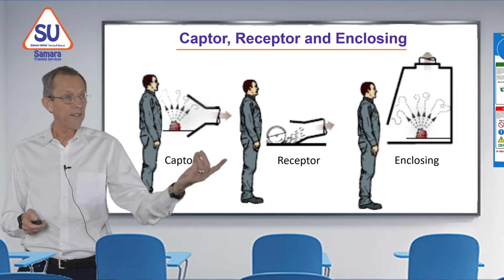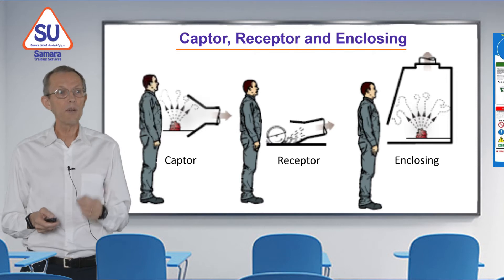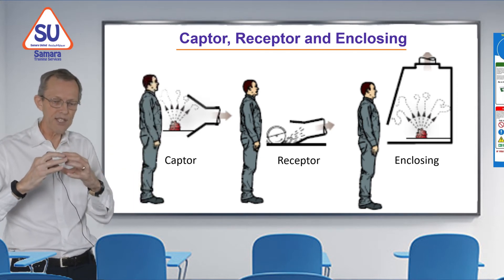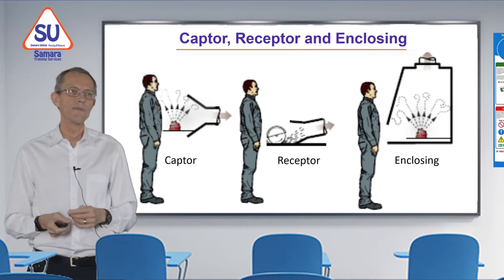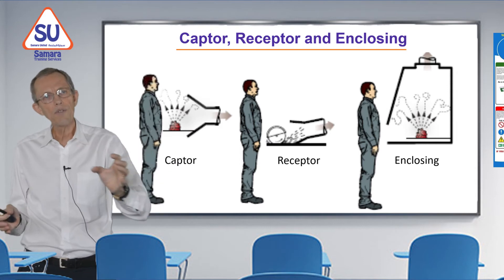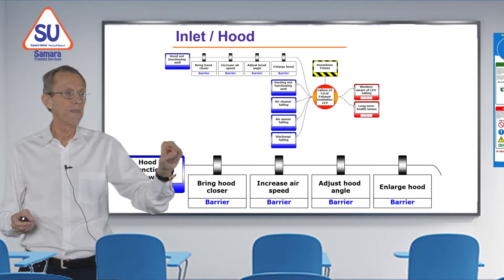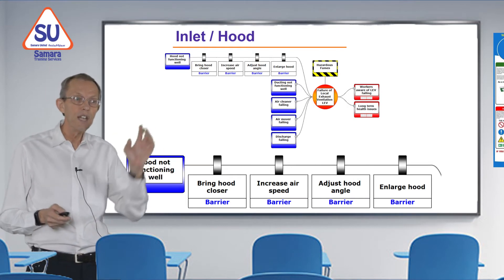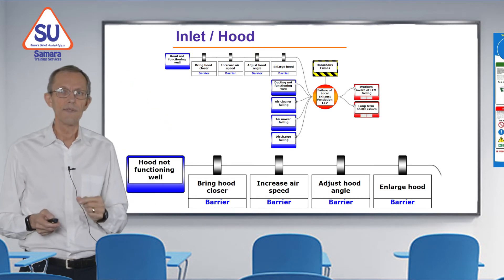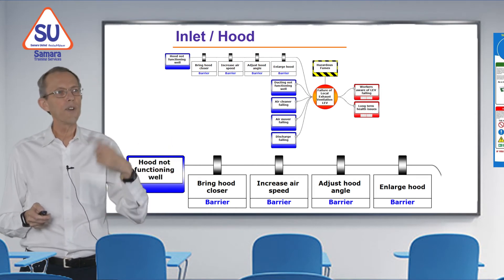The fumes on the right-hand side — the captor — the fumes are produced vertically but we're catching them horizontally. In the middle, the receptor, the sparks from the grinder come out in one direction so we put the hood to catch them in that direction. On the last one, the enclosing type, fumes come from everywhere but we have an enclosure around it and suck air out the top. On the bow tie, the first threat line enlarged at the bottom shows: hood not functioning — we bring the hood closer, increase the air speed, adjust the angle, or enlarge the hood — four barriers.